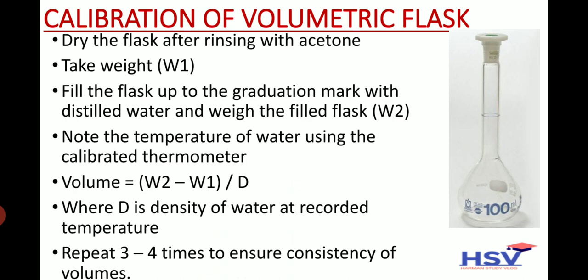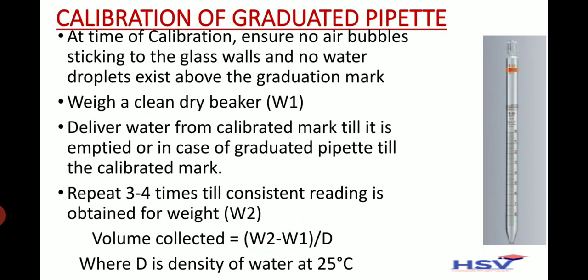Note the temperature of water using the calibrated thermometer. Volume = (Weight 2 − Weight 1) / d, where d is the density of water at the recorded temperature. Repeat three to four times to ensure consistency of volumes.